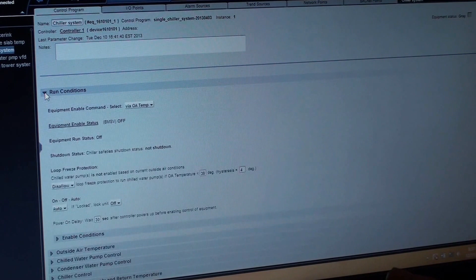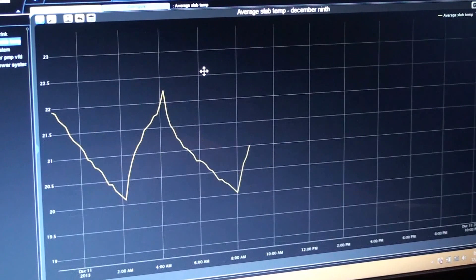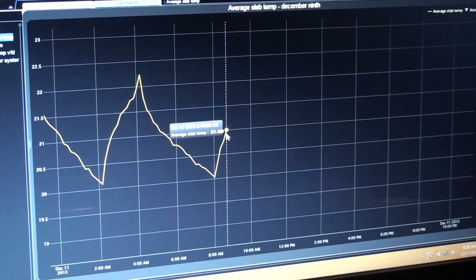So we're going to put 0.50, go up to accept. It locks that value into the processor, and we can leave that screen, back up into slab temperature, go back up to trends to bring the graph back up. We can slide, scale over. Temperature right now is 21 degrees. That's basically how you will set the ice temperature on the chiller.